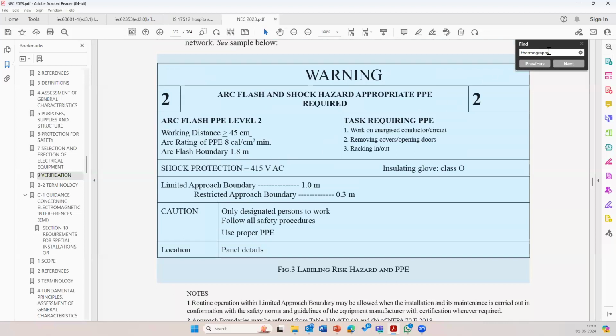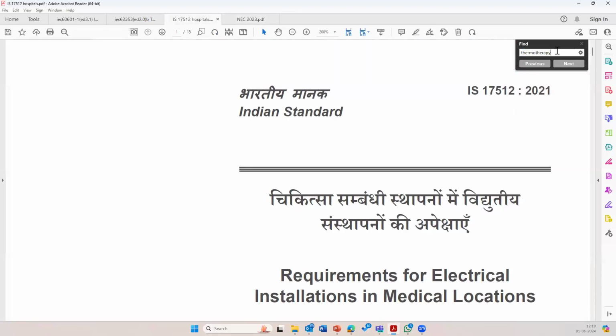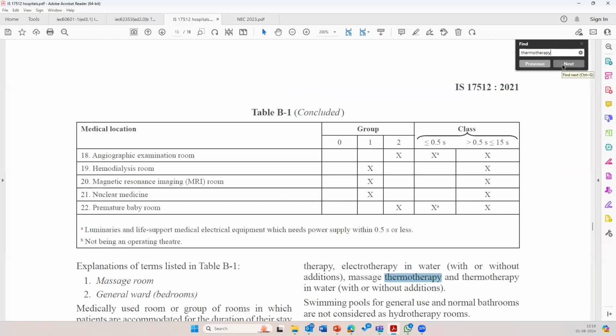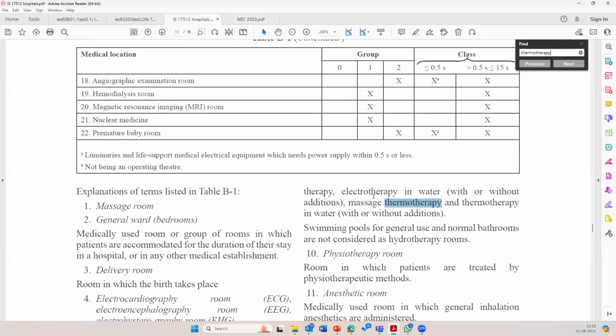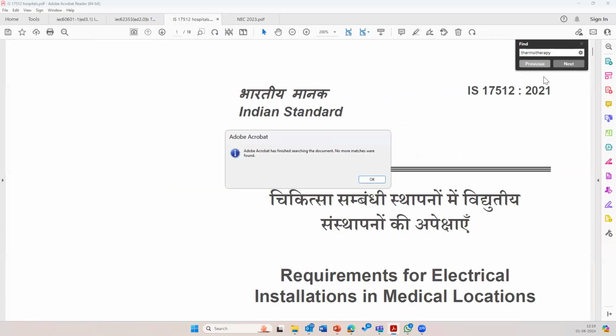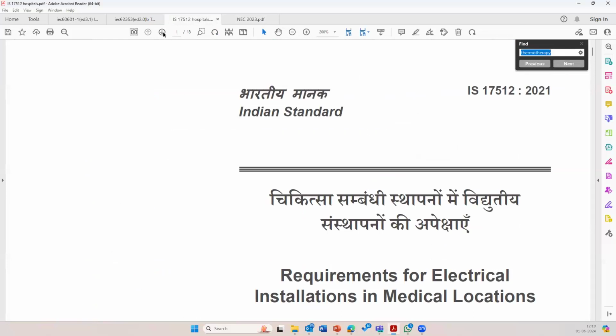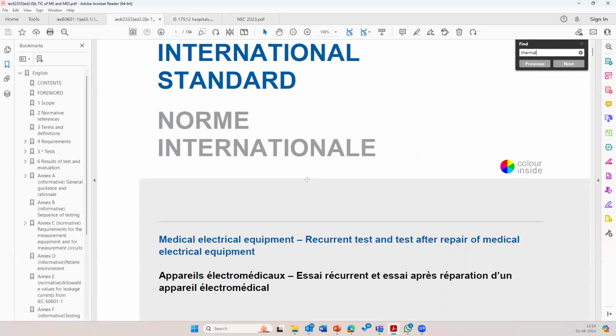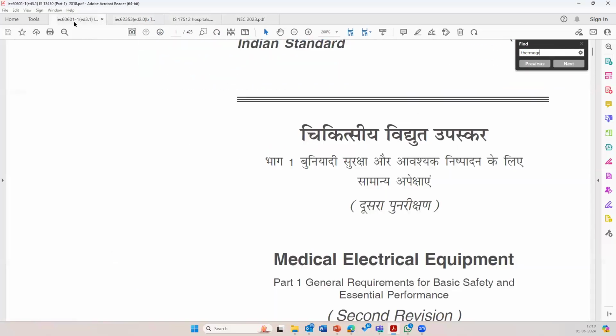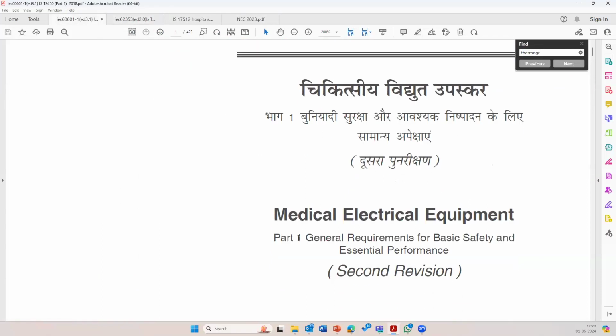This is also not a part of it, not a mandatory requirement. Thermography is not recognized in National Electrical Code or in any of the low voltage electrical safety standards. It is not recognized. Now I am taking you to IS 17512. The word thermography is used there, but for massage thermography, that is not thermal imaging, but something else. So the word thermal imaging or thermography itself is missing from all these national standards.